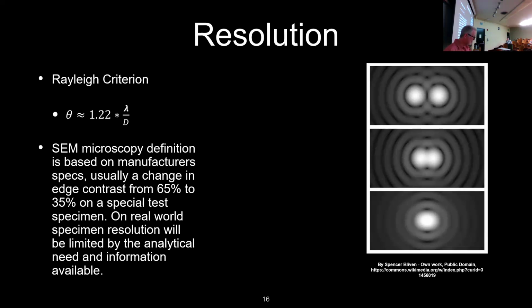With SEM and FIB microscopy definitions, I think we lie a little bit here, because we use an edge contrast methodology. That means there's a test specimen like I showed you previously, although we would use gold on carbon for this microscope because it's extreme high resolution. We look for a change in contrast from 65% to 35%. The Rayleigh criterion would imply that we have to go from 90% to 10%. And so our 0.5 nanometer resolution might mean we can see particles maybe 3 or 4 nanometers in size.